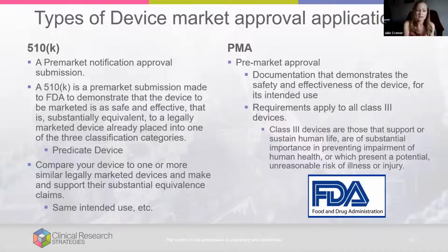You're comparing your device to one or more predicate devices, or legally similar, legally marketed devices. And you're going to make your claim that you are substantially equivalent to that device. One of the main things is to have the same intended use, which we just talked about. So that same intended use, that very defined, injecting insulin into the bloodstream to increase insulin levels.